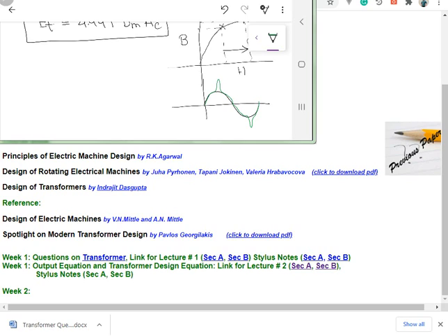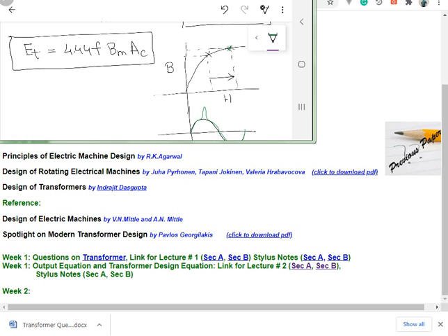Now these high frequency currents are going to pose problems inside your transformer, maybe to the other supply attached with that transformer. Otherwise it's going to run very fine, and this is the same problem also in fans or motor design. If your manufacturer, like normally the manufacturers in Pakistan, always want to earn fast, so they always choose a value of B that is more in the saturation region. More in the saturation means that you are having a huge current spike.